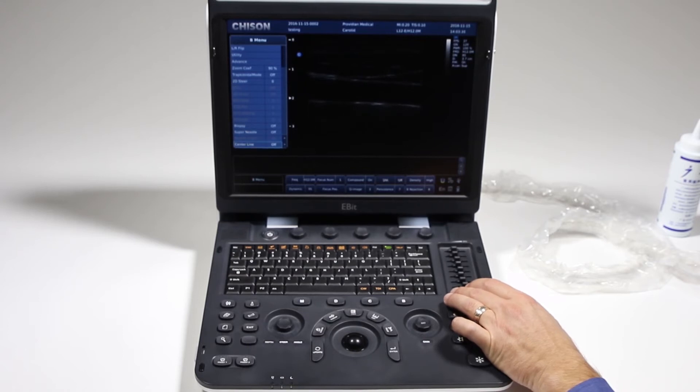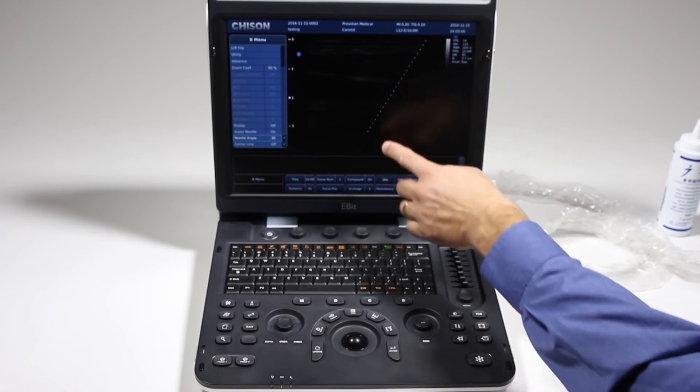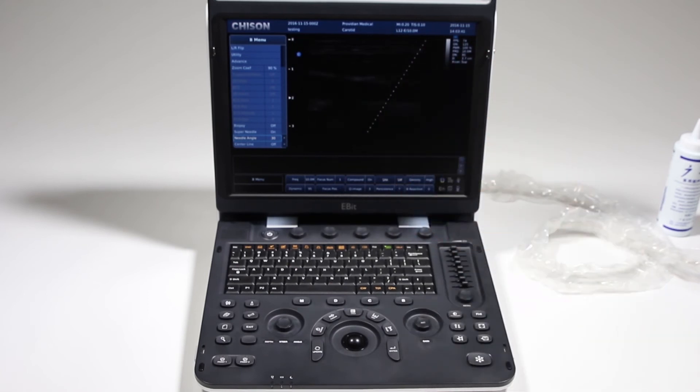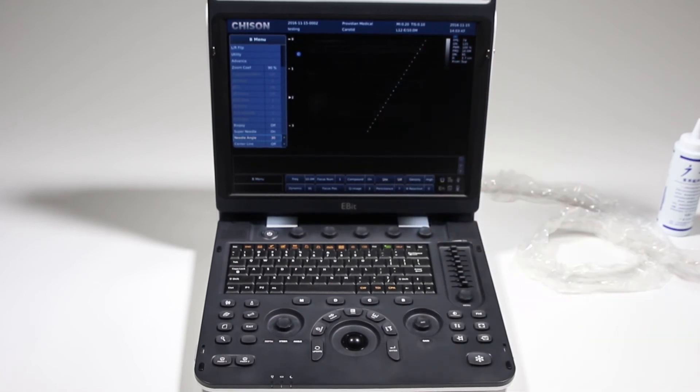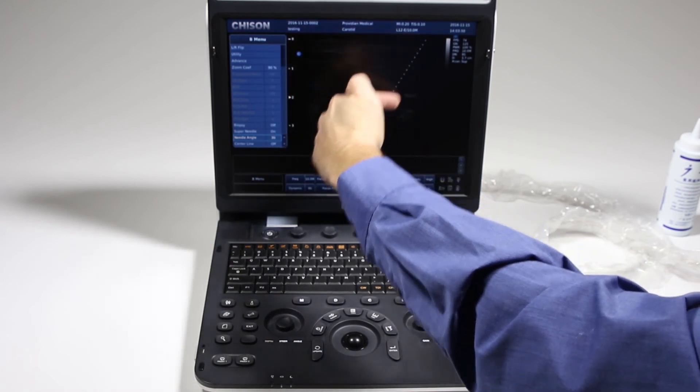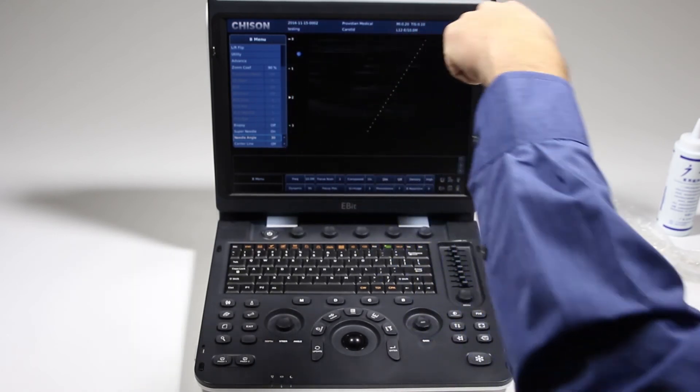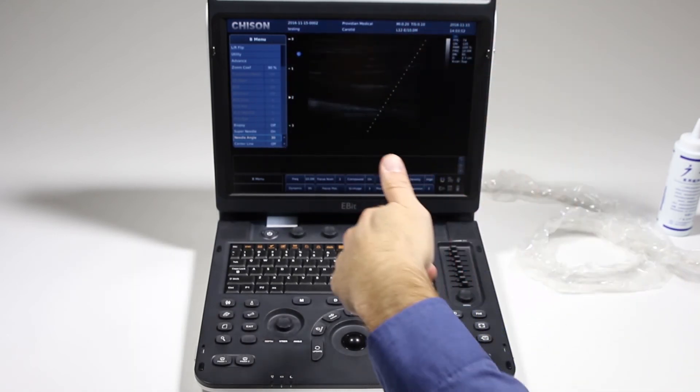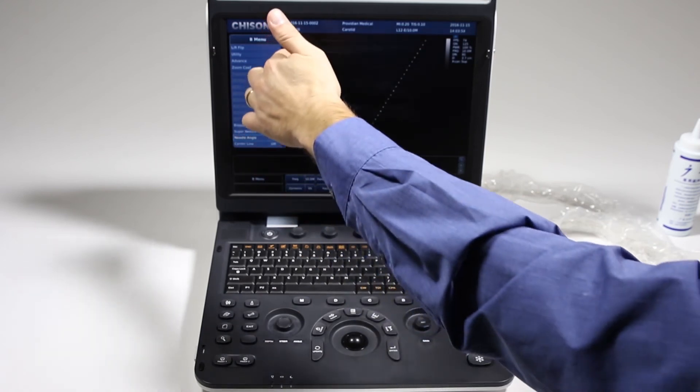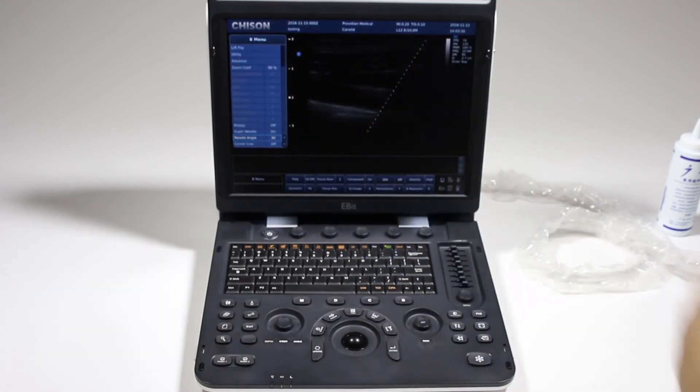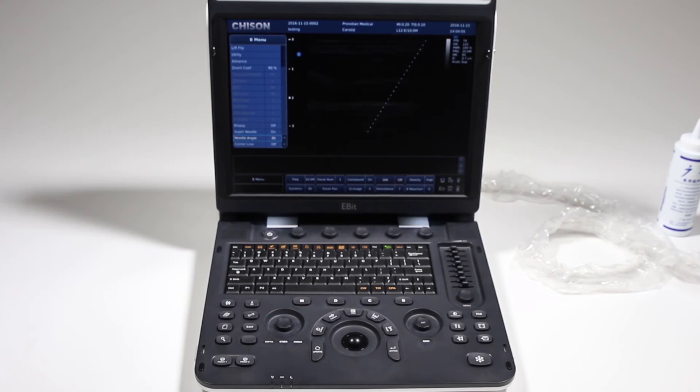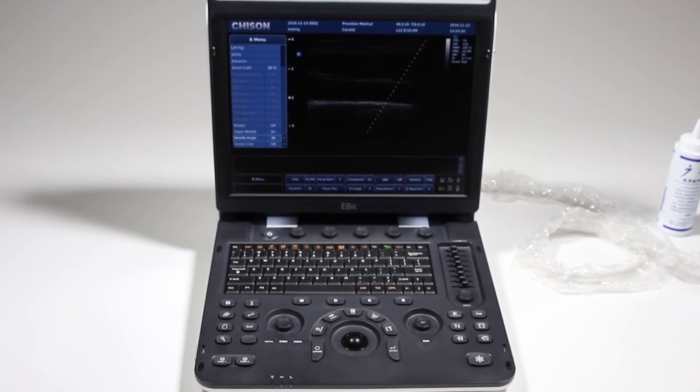We showed the biopsy and super needle in the first video, but I will address the super needle again. This line here shows where the needle should be aimed. Your needle should be coming in and being perpendicular to this line. You don't want to go along the line like you would in a biopsy. You would come straight across here and make it perpendicular and you would see the needle. It has a dramatic effect on how bright that needle is. With that super needle off, it's often dark and you can only see the needle tip. But when you use that super needle, it will show you a much brighter image.